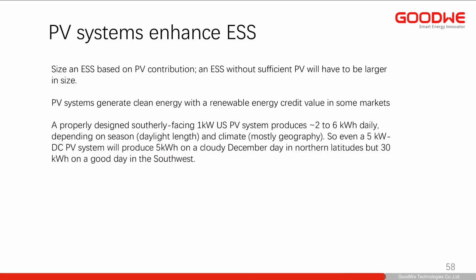Just a quick word here: while you can get a battery inverter, please consider PV systems. I know some installers won't do an ESS without PV. You're saving on the size of the ESS, and in some areas the energy from the PV system is more valuable because of its clean energy credit. But remember, even though your PV system might be glorious in summer, producing 30 kilowatt hours on a sunny day, in winter on December 22nd it might only produce 5 kilowatt hours on a cloudy day, and that might be the day you lose power. So you want the PV system's contribution to the ESS to be based on that worst-day scenario.